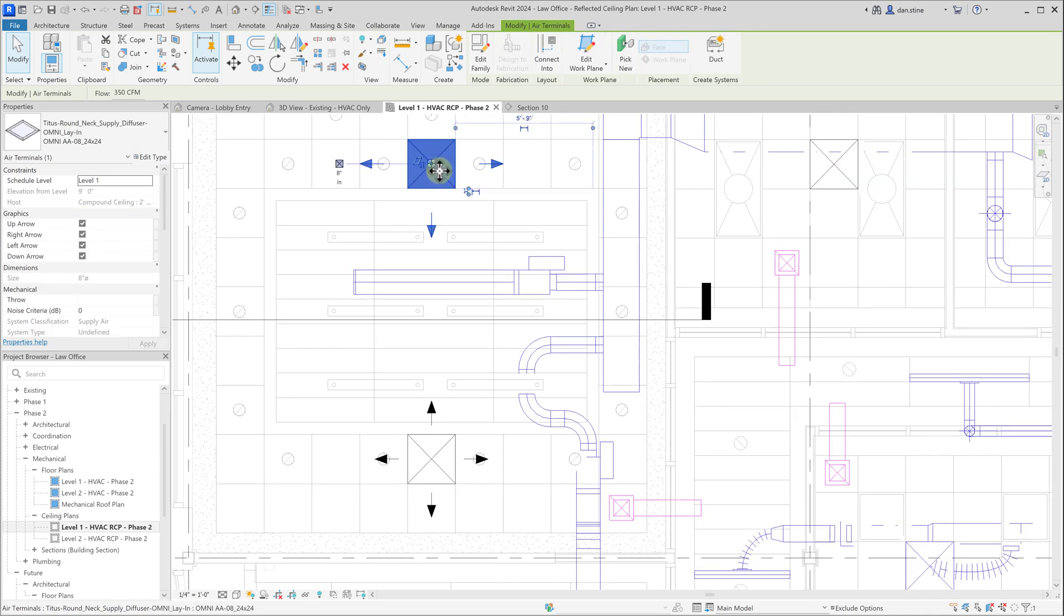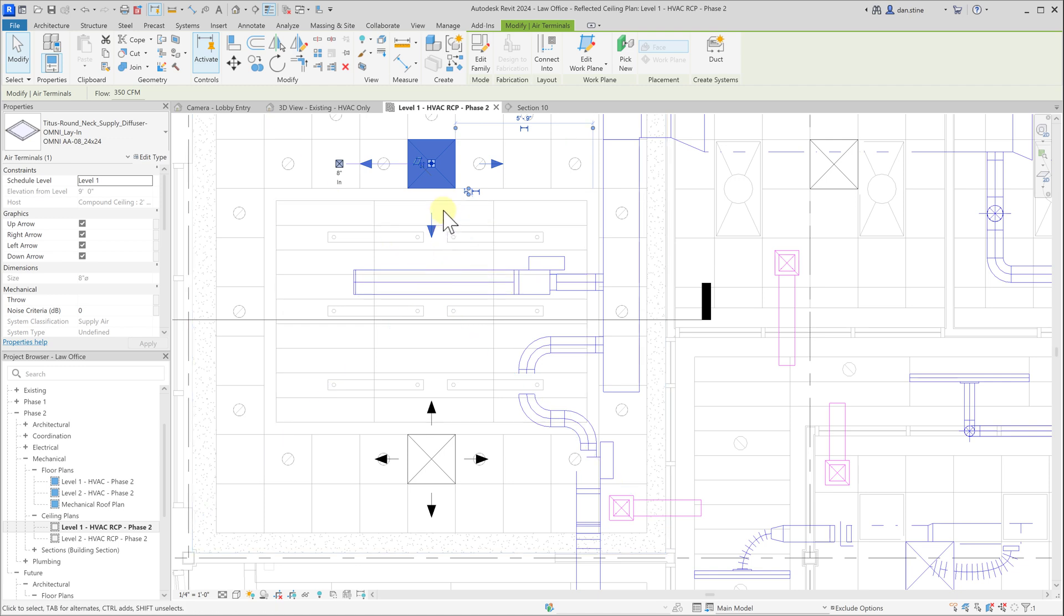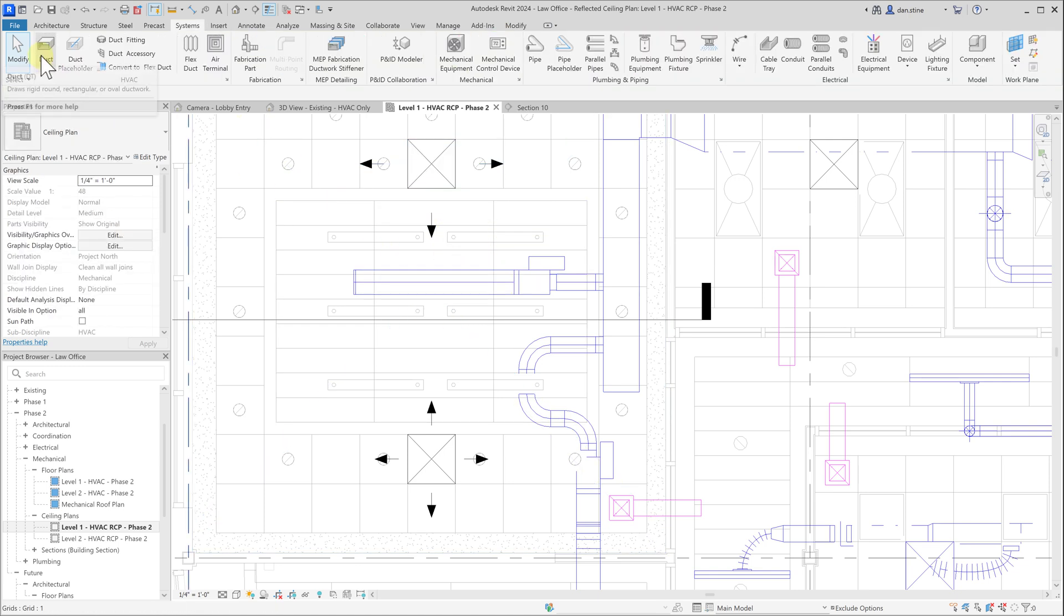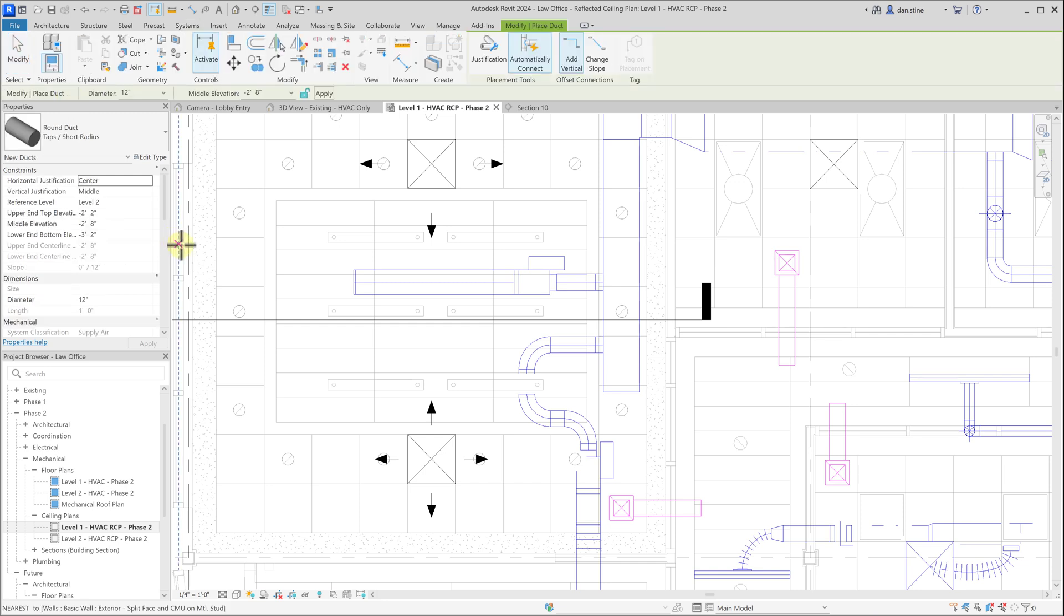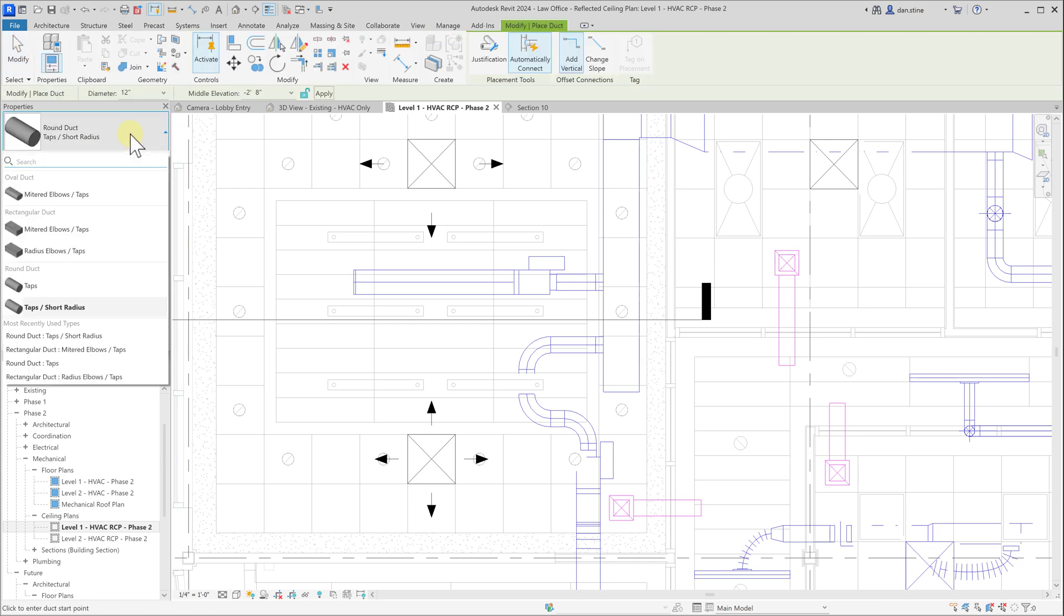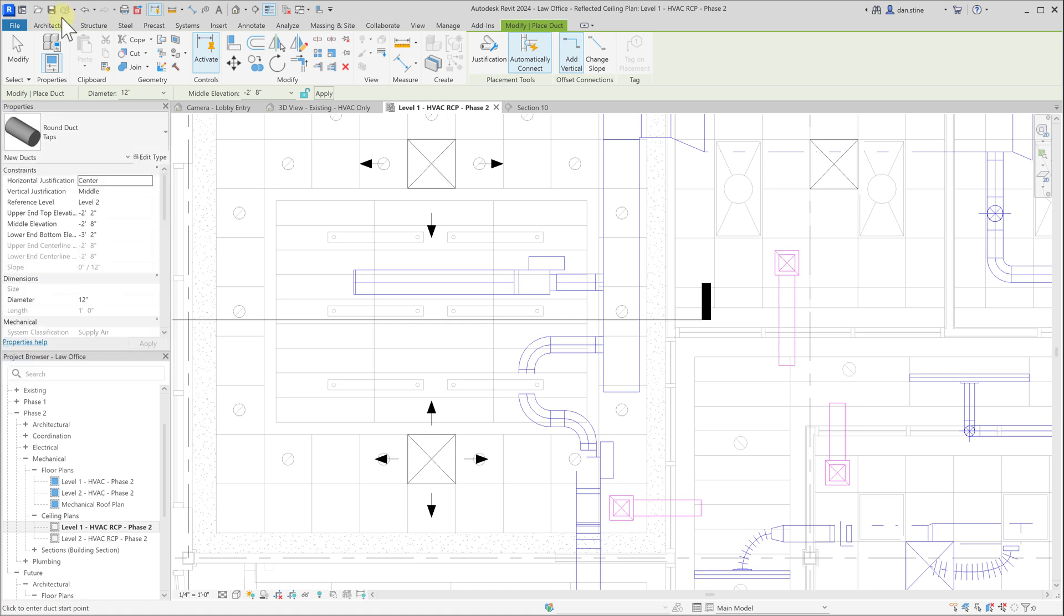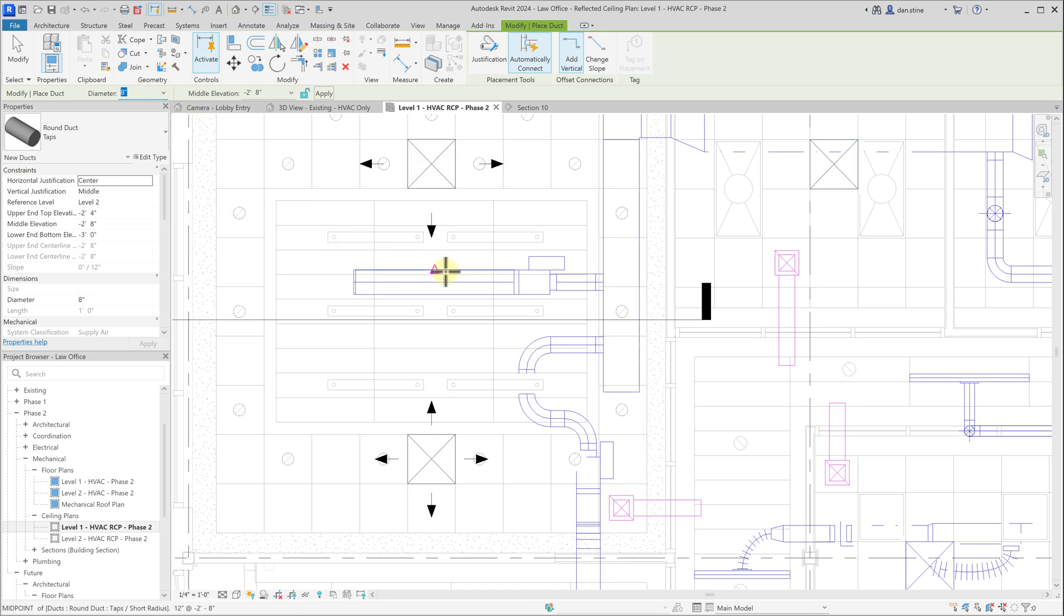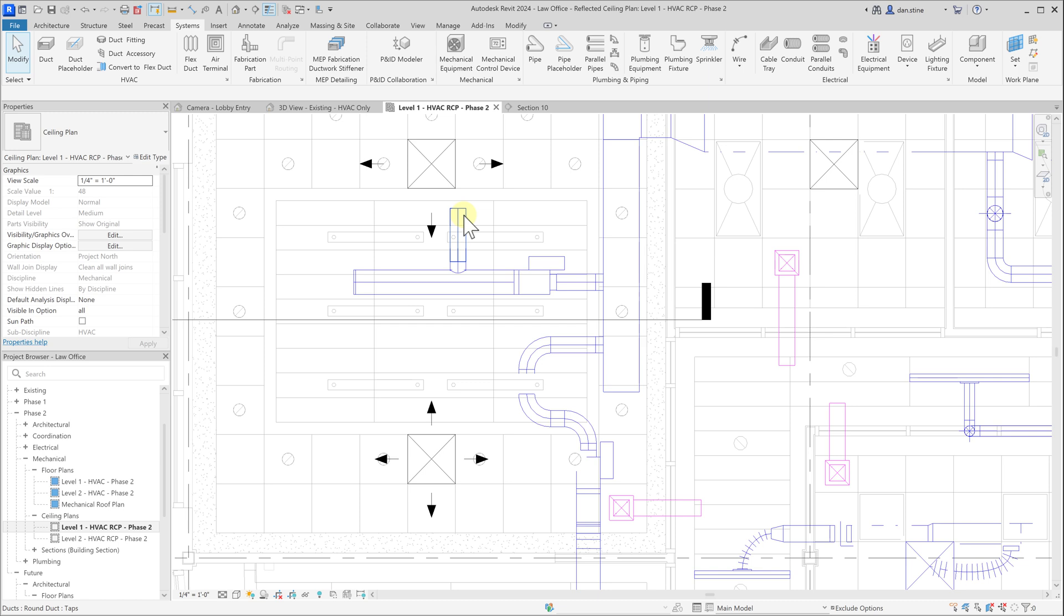Next, we're going to run duct from this duct coming from the VAV box over towards this air terminal that we added. We're going to select the duct command. Then in the type selector, we'll select round duct with taps and set the diameter to eight inches. We'll pick a point just short of where the air terminal is and hit escape a few times to end the duct command.